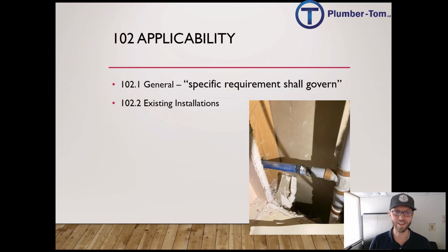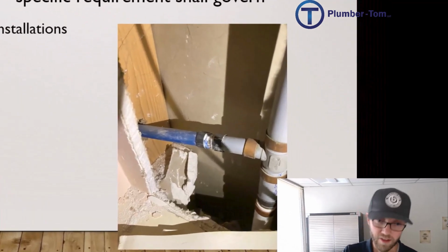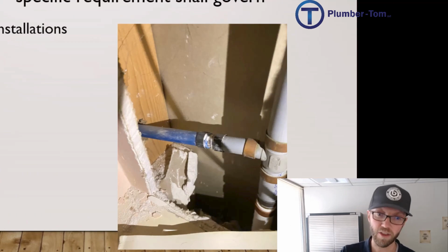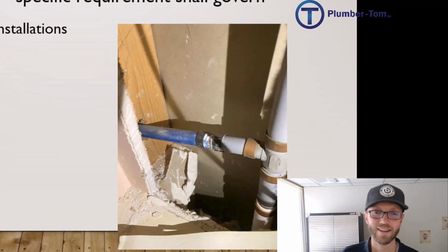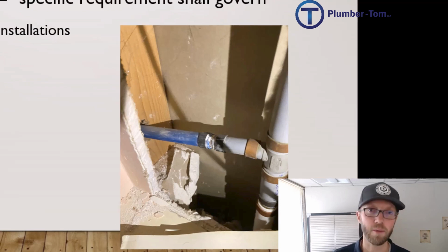Well, yeah, if you can get that done, and I've had customers that had me do that. But otherwise, if it's existing and it's not leaking, well, you can leave well enough alone. This picture shows connections of the more up-to-date PEX connecting to that polybutylene where they either had leaks or had made changes. But again, you don't have to rip a whole building apart just because it doesn't meet code at the moment. But if there's a problem, that's when you address it.